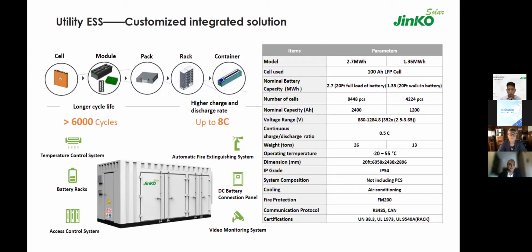As an example of the parameters, this is like a 20 feet container. If we do a walk-in design, which allows a person to go in to do installation, testing, and checking, we can store around 1.4 to 1.6 megawatt hours total battery capacity.